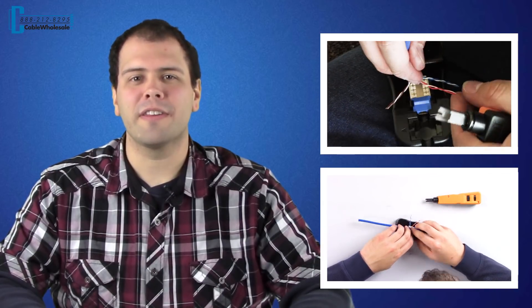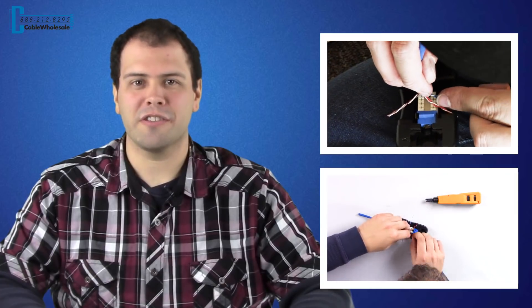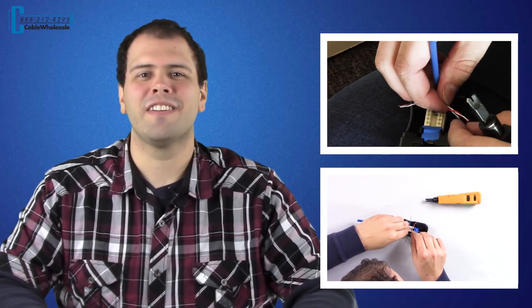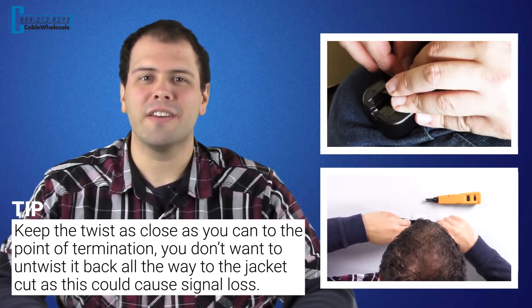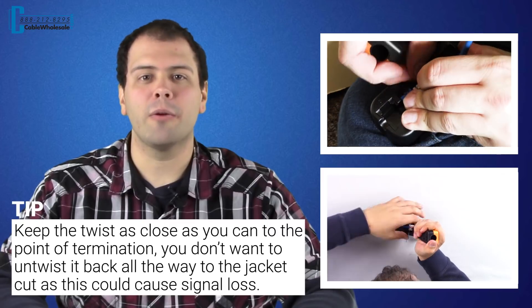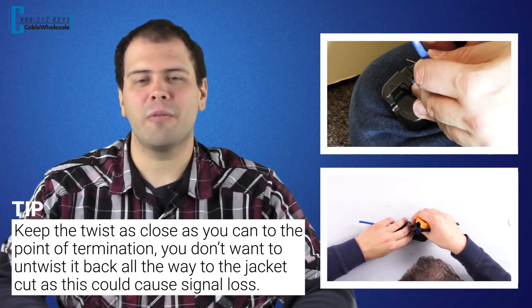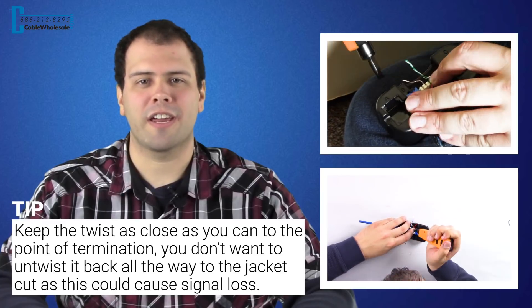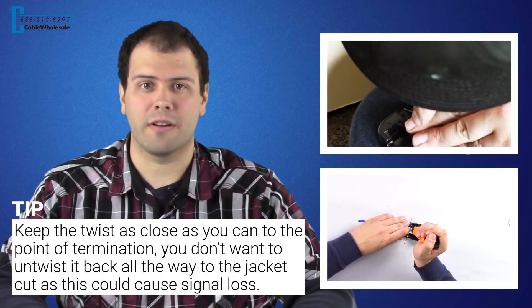Untwist the four pairs of the stripped cable and place the cable in the proper orientation to prepare for punch down. A helpful tip when doing this is that you want to keep the twist as close as you can to the point of termination. You don't want to untwist it back all the way to the jacket cut as this could cause signal loss.